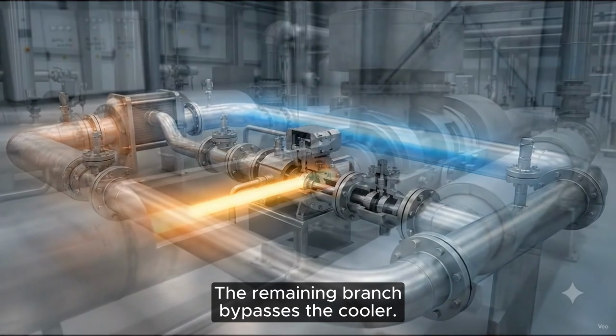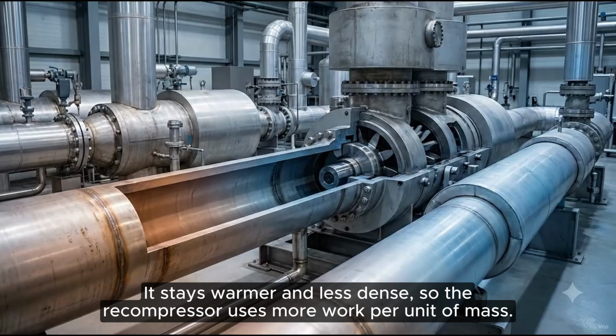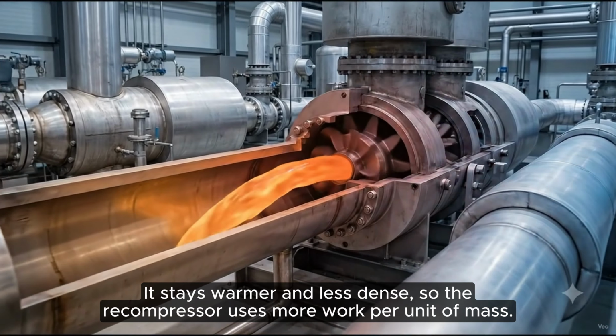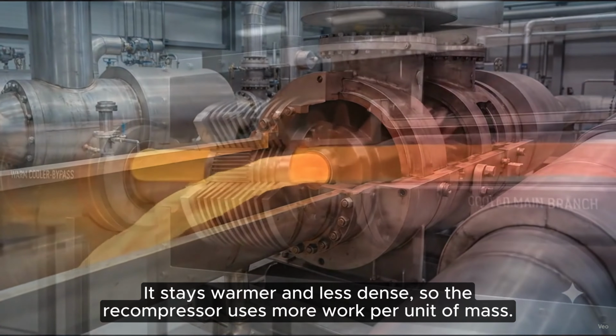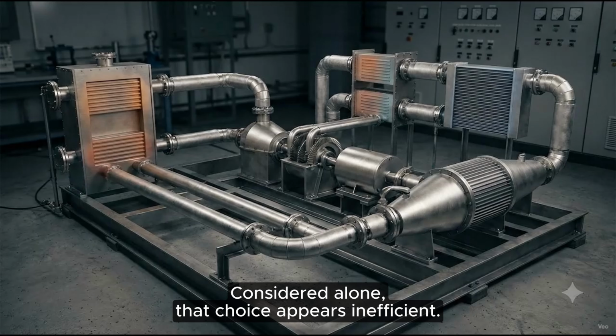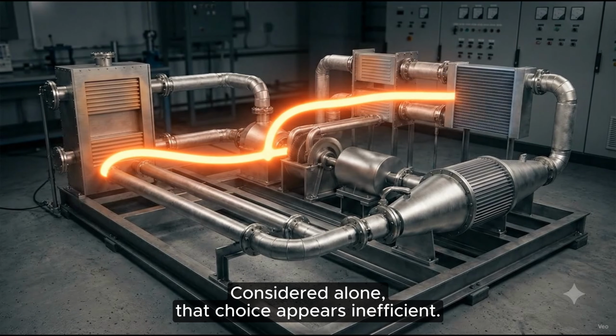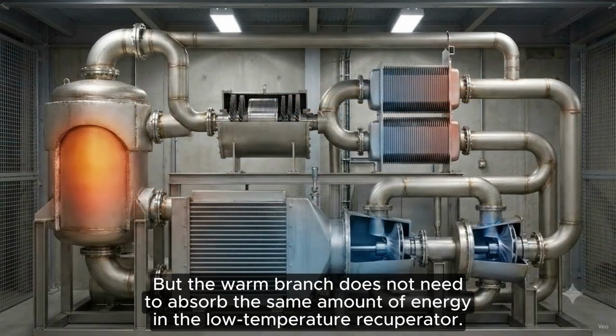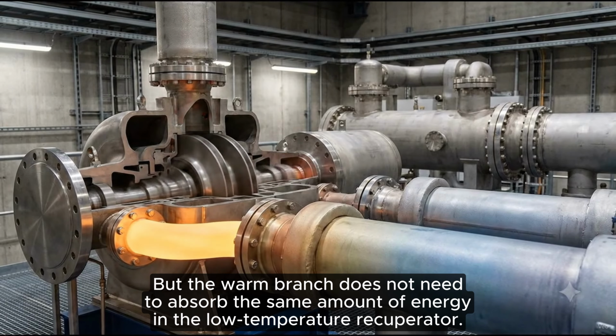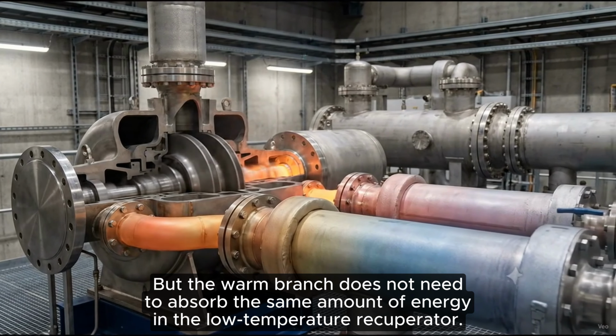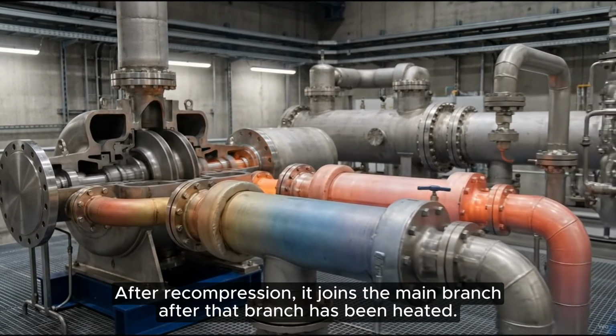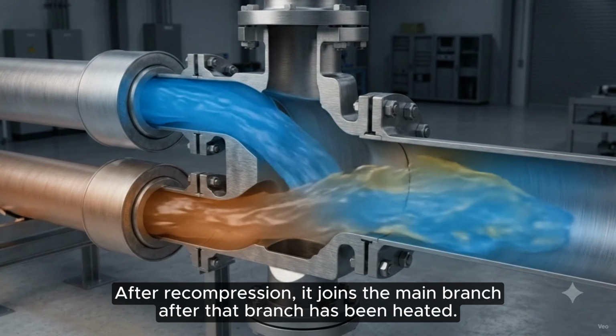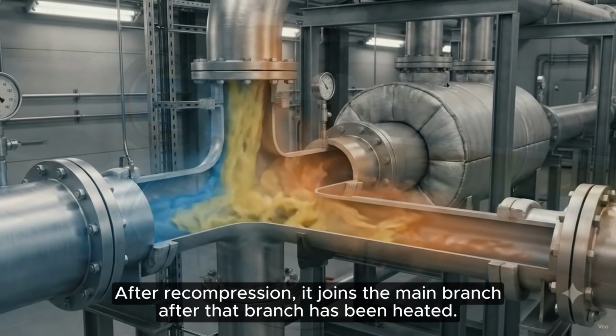The remaining branch bypasses the cooler. It stays warmer and less dense, so the recompressor uses more work per unit of mass. Considered alone, that choice appears inefficient. But the warm branch does not need to absorb the same amount of energy in the low-temperature recuperator. After recompression, it joins the main branch after that branch has been heated.